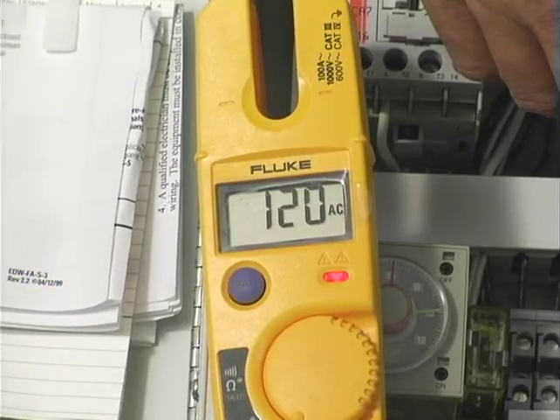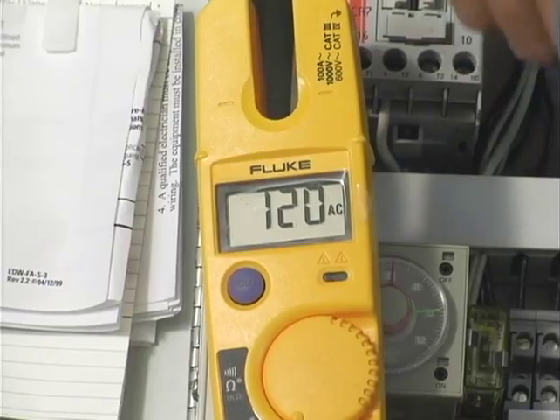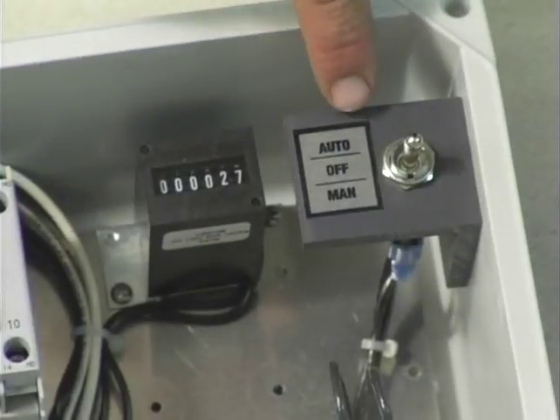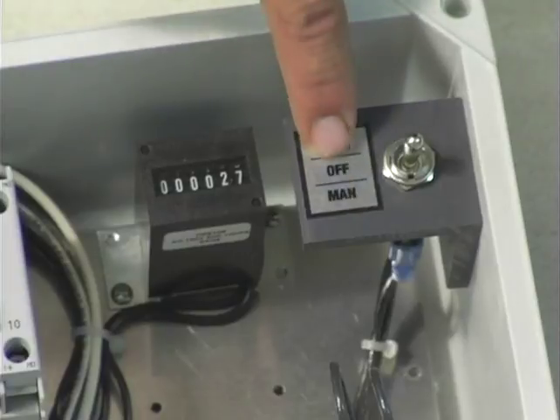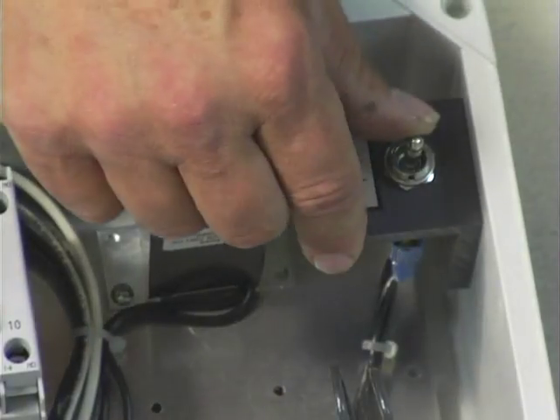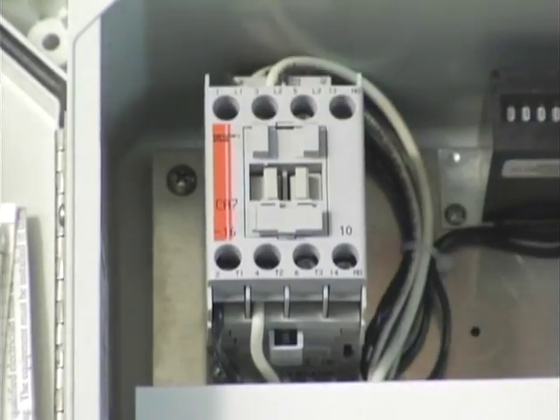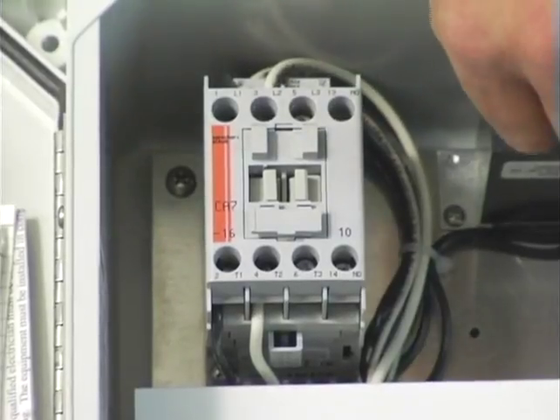So we've got incoming power into the control panel. Now what we're going to check is you've got your auto, manual, and off switch. If we switch it into manual, the motor contactor engages. We know that there's no problems with the motor contactor.